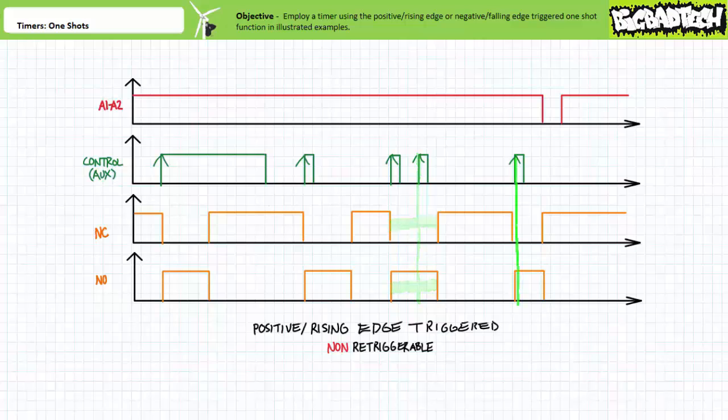The one tricky part of this timing diagram is experienced here when the timer experiences a loss of external power during an ongoing one-shot. Ordinarily, the contacts associated with the one-shot would assume their opposite activated state for a period of 5 seconds when triggered. The loss of the external power is kind of like a reset signal in that when the timer loses external power, the associated contacts instantly return to their deactivated state, thus overriding or resetting the ongoing one-shot.